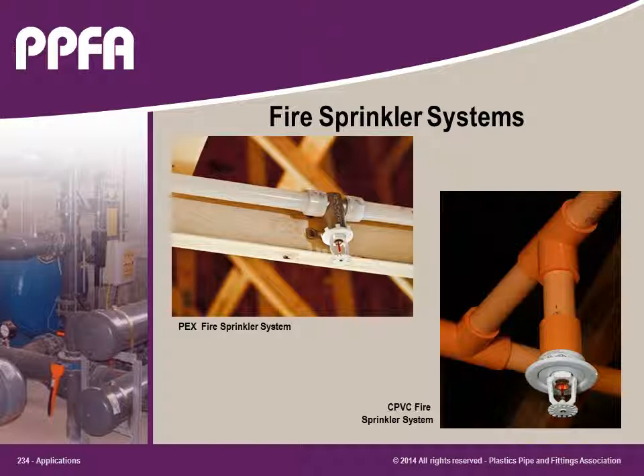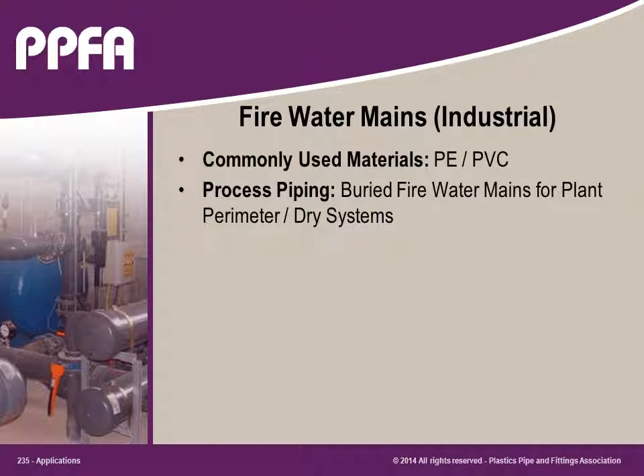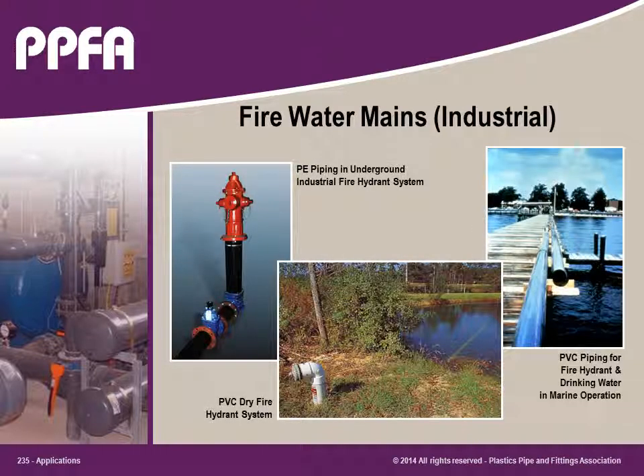Usually, CPVC piping is installed in standalone systems incorporating a separate piping system and water source. PEX piping is normally used in a multi-purpose system combining with an existing cold water plumbing line. Both systems are well tested and have proven to be very successful. When industrial fire hydrant piping is required and there is an aggressive soil condition, thermoplastic piping materials are most commonly used.